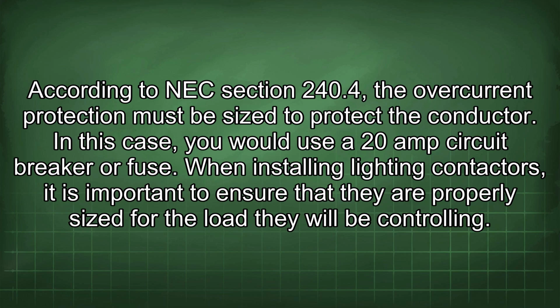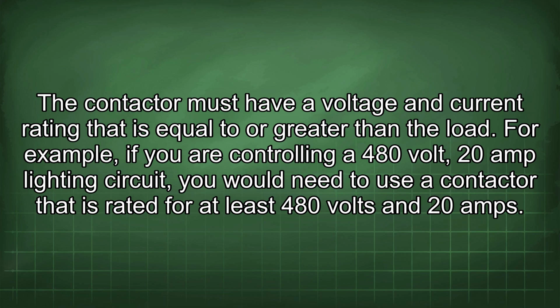When installing lighting contactors, it is important to ensure that they are properly sized for the load they will be controlling. The contactor must have a voltage and current rating that is equal to or greater than the load. For example, if you are controlling a 480 volt 20 amp lighting circuit, you would need to use a contactor that is rated for at least 480 volts and 20 amps.